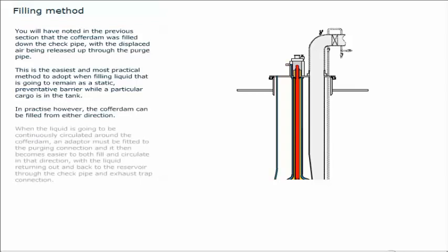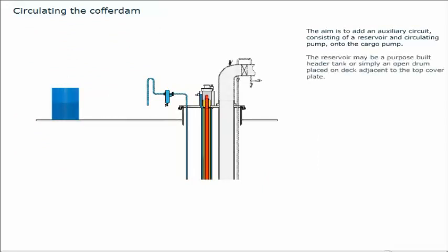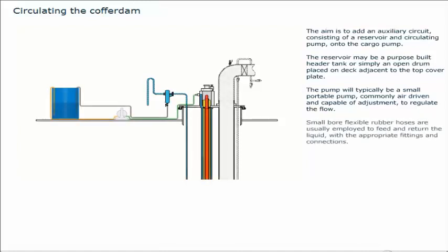When the liquid is going to be continuously circulated around the cofferdam, an adapter must be fitted to the purging connection, and it then becomes easier to both fill and circulate in that direction, with the liquid returning out and back to the reservoir through the check pipe and exhaust trap connection. The aim is to add an auxiliary circuit, consisting of a reservoir and circulating pump, onto the cargo pump. The reservoir may be a purpose-built header tank or simply an open drum placed on deck adjacent to the top cover plate. The pump will typically be a small portable pump, commonly air-driven and capable of adjustment to regulate the flow. Small bore flexible rubber hoses are usually employed to feed and return the liquid, with the appropriate fittings and connections.